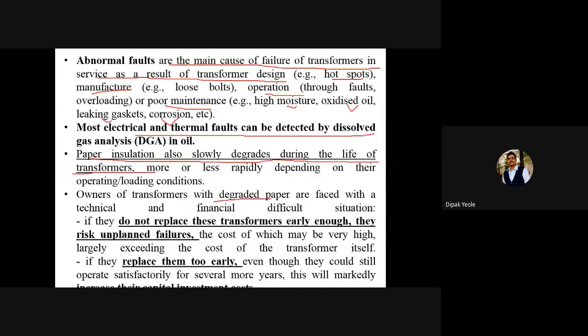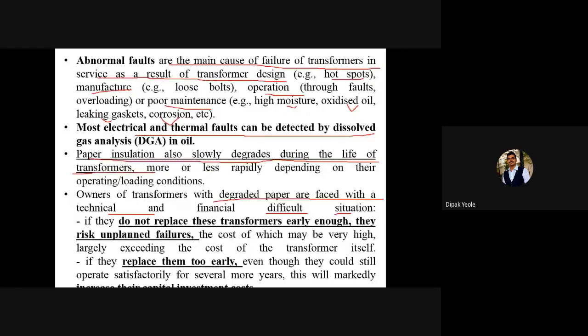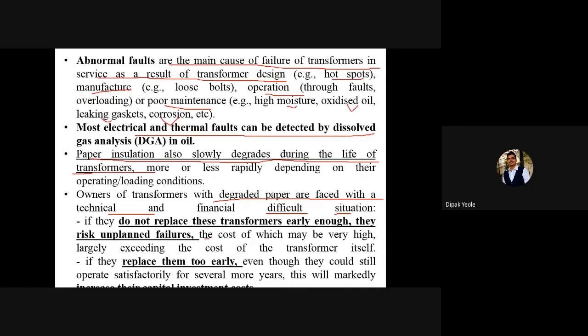We are interested in different tests. The DGA test you have studied today. If you are conducting this test routinely or regularly, you are taking care of the transformer. But if you do not replace the transformer in time, it tends to unplanned failure, and the cost of which may be very large — largely exceeding the cost of the transformer itself. You have to compare the carbon dioxide and carbon monoxide levels with the standard one to make a replacement decision.